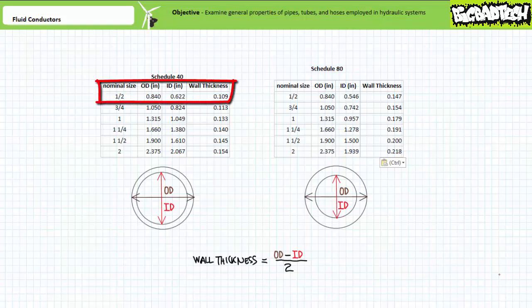For example, a nominal schedule 40, half inch pipe has an OD of 0.84 and an ID of 0.622 inches. This corresponds to a wall thickness of approximately 0.109 inches.